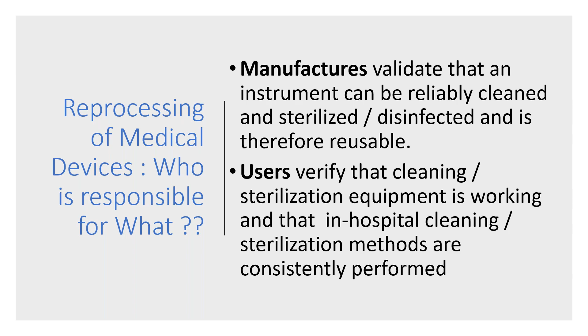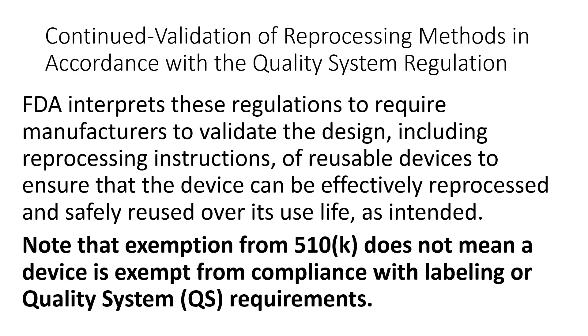So going back to the validation section of that document, FDA interprets this regulation to require manufacturers to validate the design, including reprocessing instructions of reusable devices, to ensure that the devices can be effectively reprocessed and safely reused over the life of that device. And note the exemption from 510(k). Those 43% that we said are exempt, that does not mean the device is exempt from compliance with labeling, which includes the IFU, and the quality system when FDA goes to the device manufacturer.